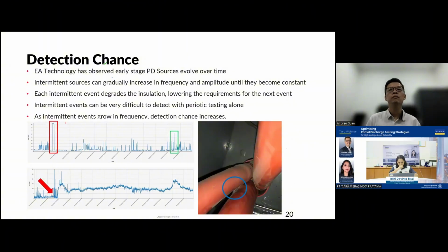This will happen if you are lucky — if the failure never happens before you go back, you can still detect it. But it also depends on how frequently you go back to check the switchgear or transformer before you can detect this intermittent PD activity.